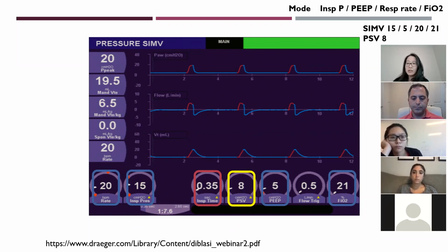These are all machine initiated. They're all following the inspiratory pressure and the time that you set. And if the patient decides to take a breath on their own, then you'll see a little blip here of that 8 going up. You would report it the following, the top as if it were pressure AC, so SIMV, inspiratory pressure 15, you have a PEEP of 5, respiratory rate of 20, FiO2 of 21% with a pressure support of 8. Okay, any questions about this mode?